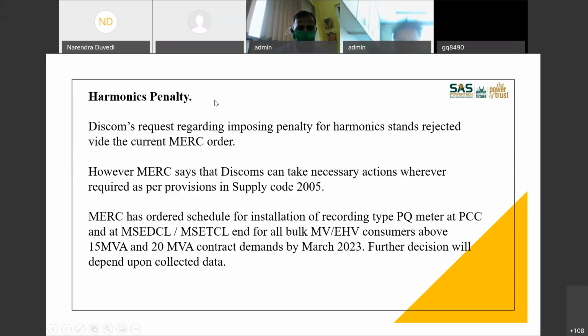See, there was talk that this particular tariff change will bring in a harmonic penalty in Maharashtra, but the request regarding imposing a penalty for harmonics stands rejected in the current MERC order. Again, for the same reason that they never had any ready data with them, so they cannot charge any penalty for the next 5 years. However, MERC says that DISCOMs can take necessary action wherever required as per the previous Supply Code 2005.